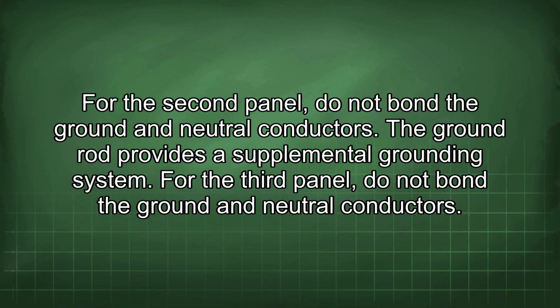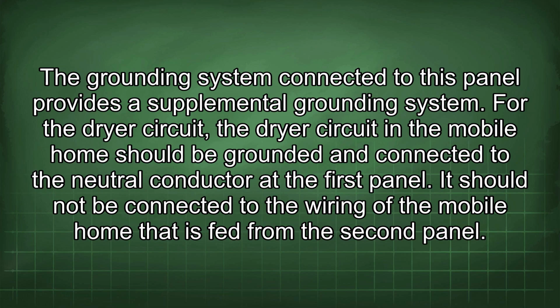The ground rod provides a supplemental grounding system. For the third panel, do not bond the ground and neutral conductors. The grounding system connected to this panel provides a supplemental grounding system. The dryer circuit in the mobile home should be grounded and connected to the neutral conductor at the first panel. It should not be connected to the wiring of the mobile home that is fed from the second panel.